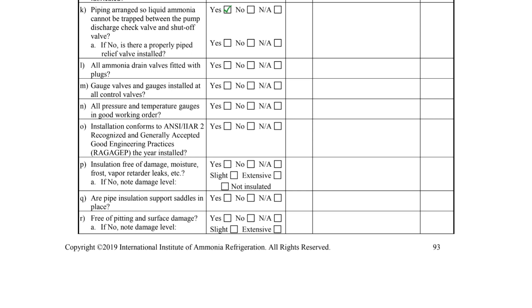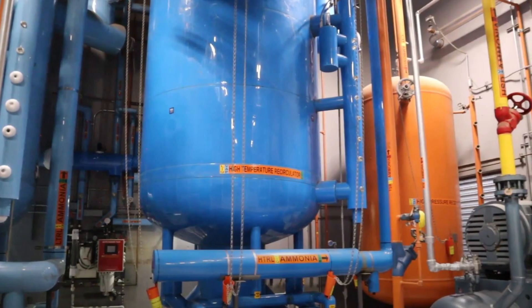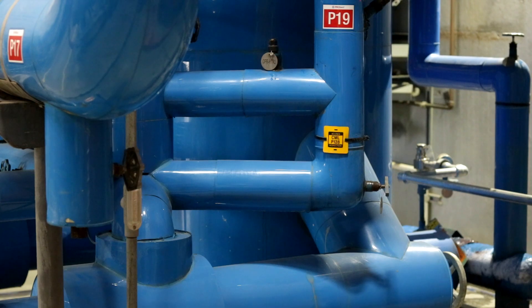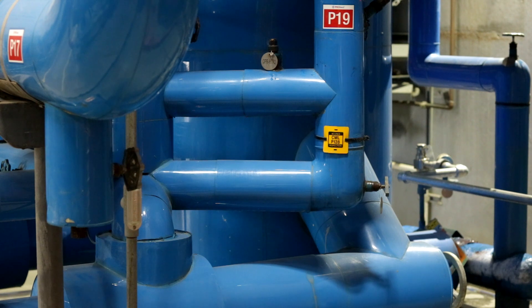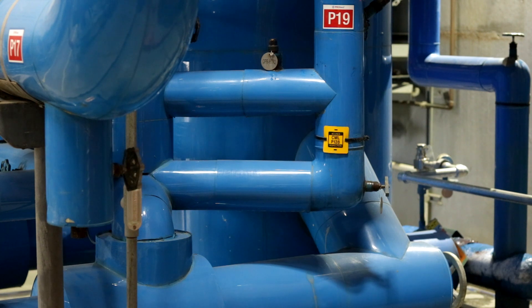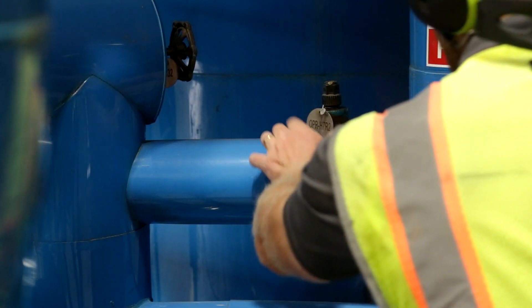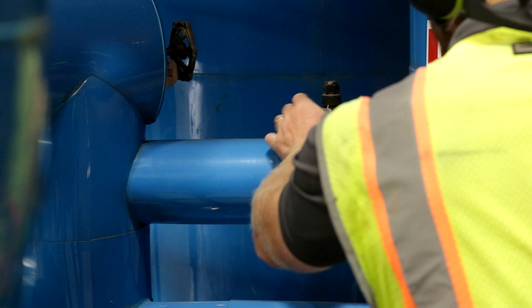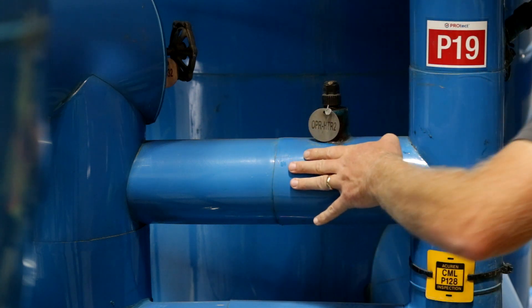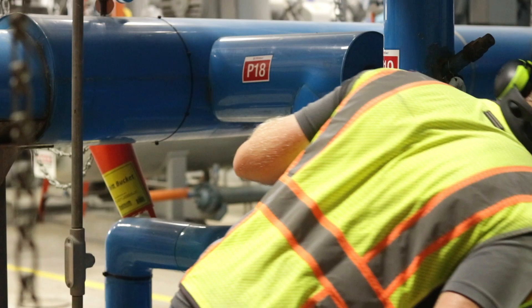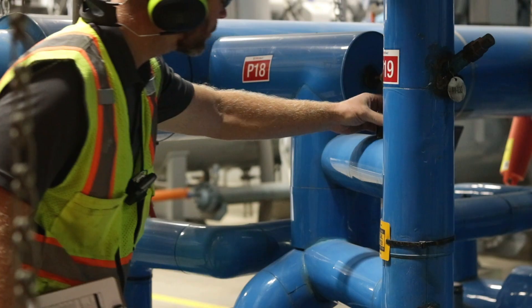Item K asks if the piping is arranged so liquid ammonia cannot be trapped between the pump discharge check valve and shutoff valve. This question is specific to systems that utilize a recirculator. In this case, a factory set relief regulator is installed between the pump check valve and isolation valve, so the configuration is compliant.